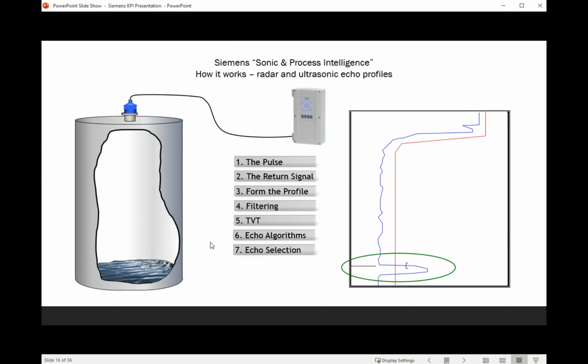In the real world, with pipes and obstructions and weld seams and concrete seams, you may have a number of echoes, and you have to deal with that. That will be handled in the 202 class that Josh was talking about, which covers some advanced manipulation of the time varying threshold. The thing that's unique here with Siemens, though, is that the TVT is dynamic, meaning it is recalculated each and every time the instrument makes a measurement.